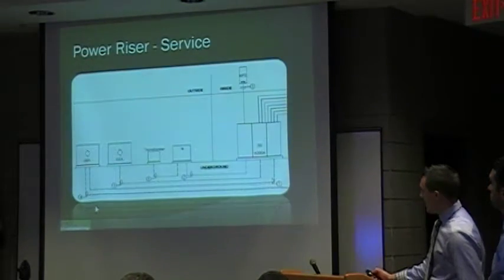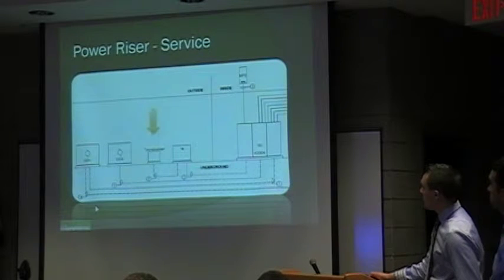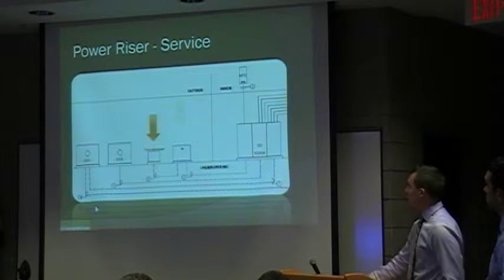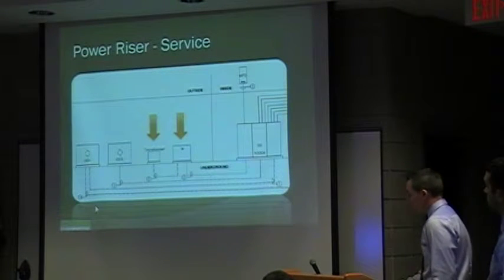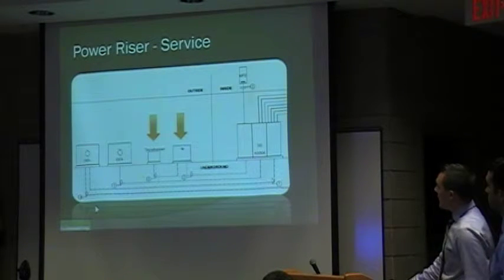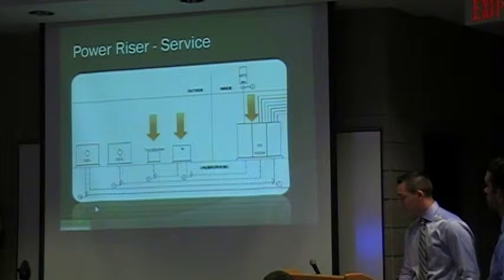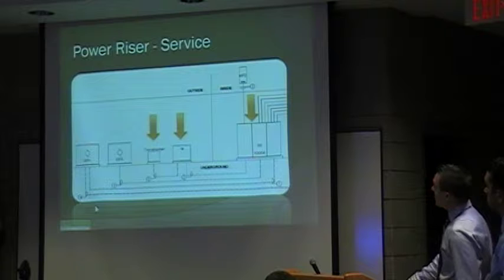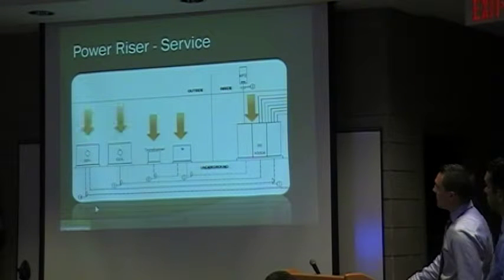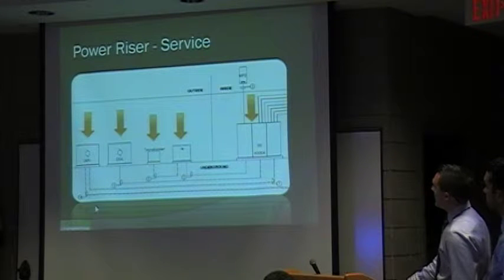We start out at our service, at our transformer. From there we move on to our terminal box. It's being fed with 480/277 three-phase 4-wire. I believe we did 11 sets of 500 KCM. Then we move on to our 4,000 amp switchgear, and it's backed up with a parallel set of generators, and it also goes to our life safety panel too.